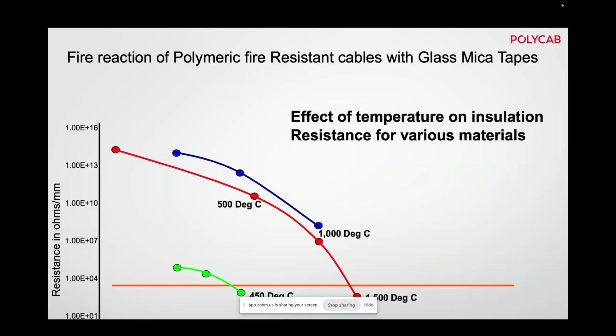Now the red color line: we have developed many insulating materials with aluminum oxide. Aluminum oxide is a good insulating material, but that also did not sustain at high temperature. Even at 1000 degrees, it has come down to less than 1 into 10 to the power 7. Only mica, the blue color, at 1000 degrees temperature is around 1 into 10 to the power 8 insulation resistance. This much insulation resistance is sufficient to pass current for 3 hours. Here the leakage current is there, but it is not so high that there will be a short circuit. That's why mica is a very safe material for use as a heat barrier, fire barrier or insulation barrier.